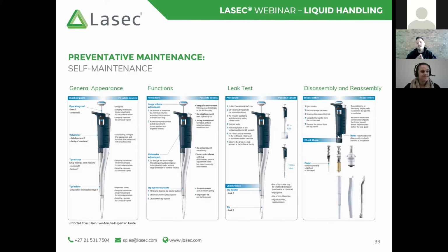If we've completed the general appearance check and the function test, and we are happy with everything so far, we will then proceed to a leak test. And a leak test serves two primary functions. The first function is to ensure that the tip that you are using fits the pipette correctly, that it's forming an adequate seal. Because of that partial vacuum that needs to be maintained, you need to have an airtight seal between the tip and your tip holder.